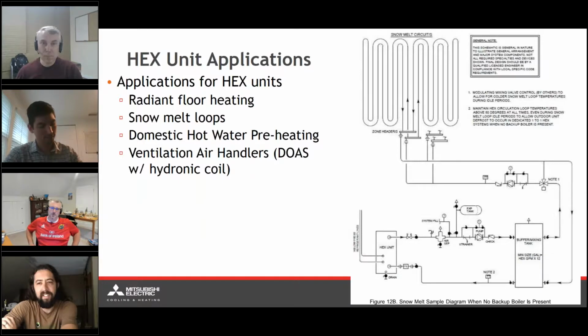So I suppose, if you had a 20-ton outdoor unit and didn't have a branch controller, how would you connect it to multiple HEX units? Is that why you need the branch controller, besides the heat recovery between the HEX units themselves? That's a good question. That was one of those where I just read that note that it must be attached to heat recovery. Let me read up as to the rationale behind that.